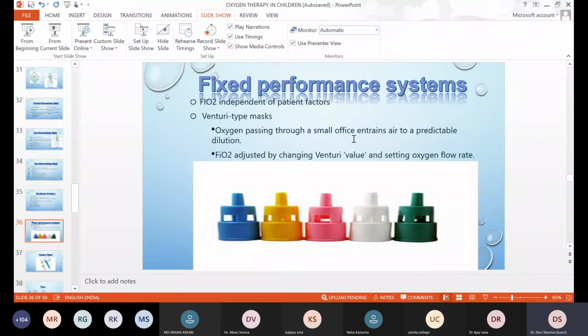When oxygen passes through a narrow orifice at high velocity, there are apertures surrounding it, as you can see in the diagram below. Air comes in through the surrounding apertures in a very fixed and predictable manner, so the FiO2 remains very constant. It cannot change with the changing demands of the patient. The FiO2 is adjusted by changing the Venturi valve and setting the oxygen flow rate. As I have shown in these diagrams, these are known as Venturi adapters. They come in different colors. There are 5 to 6 colors of adapters, and each adapter is written with the oxygen flow rate in liters per minute and the FiO2 it is going to provide.